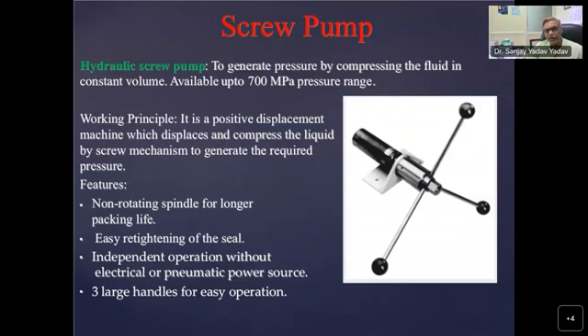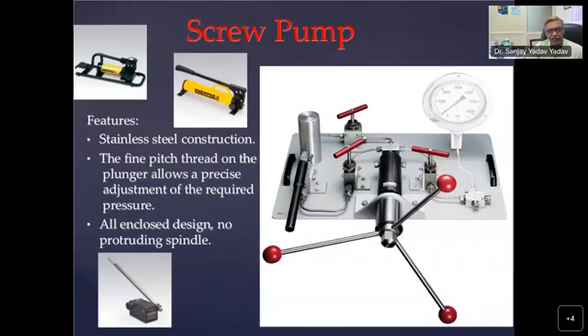Then we have the compressor. So until and unless you compress the liquid, you cannot generate pressure. To generate pressure, you need a screw mechanism pump. So these hydraulic pumps are available. The main features should be a non-rotating spindle for longer packing life, easy retightening of the seal, independent operation without electrical or pneumatic power system, and three large handles for easy operation. So these are some of the characteristics for generating pressure.